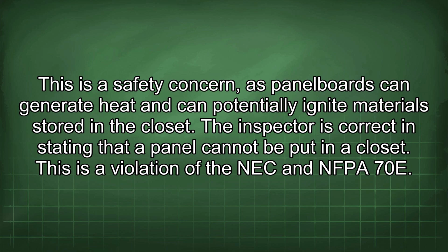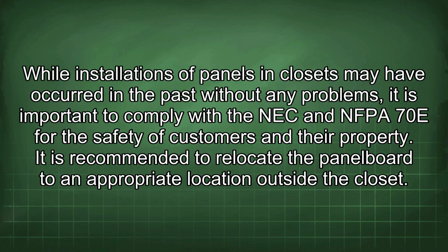The inspector is correct in stating that a panel cannot be put in a closet. This is a violation of the NEC and NFPA 70. While installations of panels in closets may have occurred in the past without any problems, it is important to comply with the NEC and NFPA 70 for the safety of customers and their property.